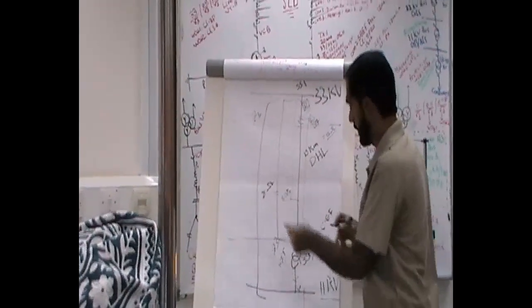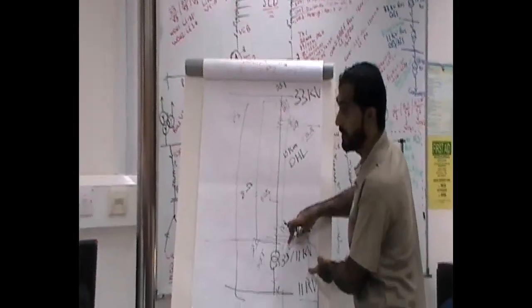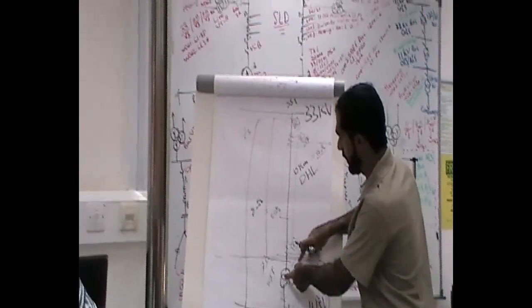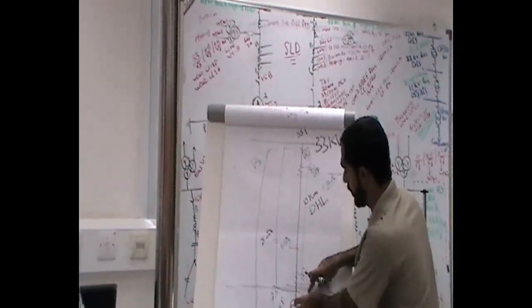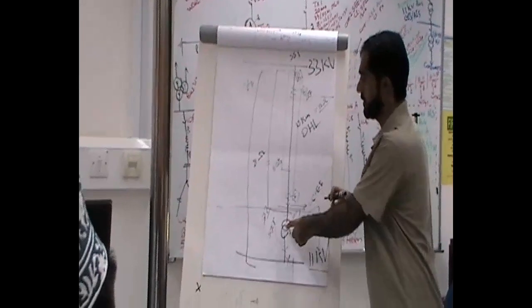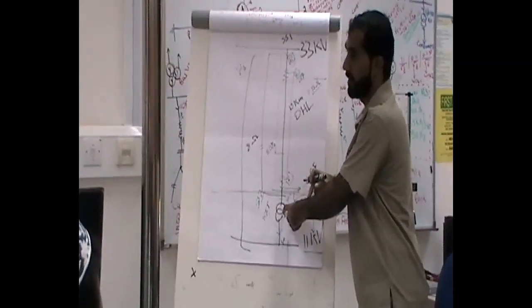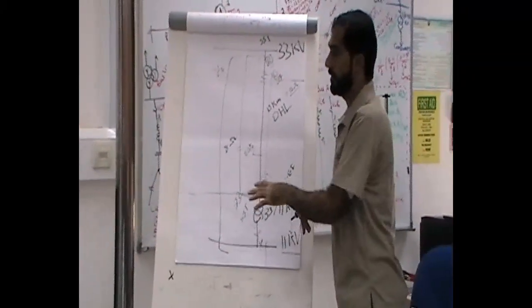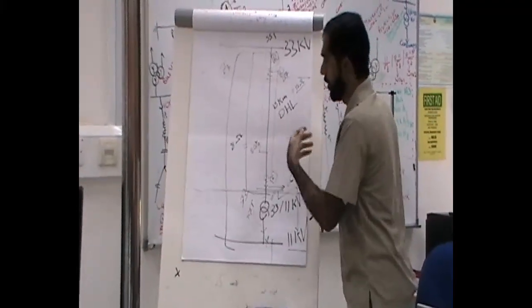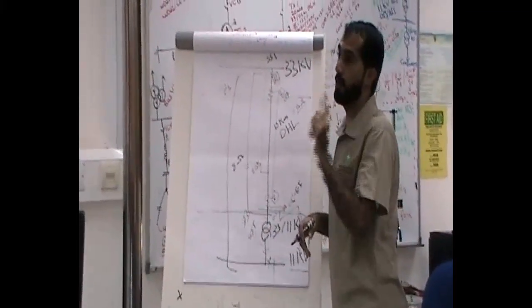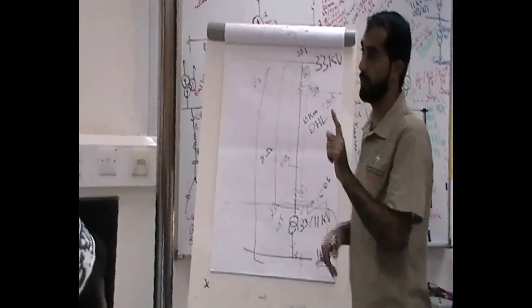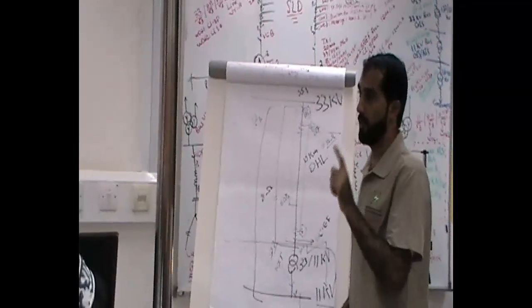If I set it to cover, for example, even 80% of this line, probably it will trip for a fault in the line and in the transformer, and I don't want that. I wanted to increase the setting of zone 3. I wanted it to go further but not to trip on the load. That's my concern in zone 3. Yes, it should not operate on the load.